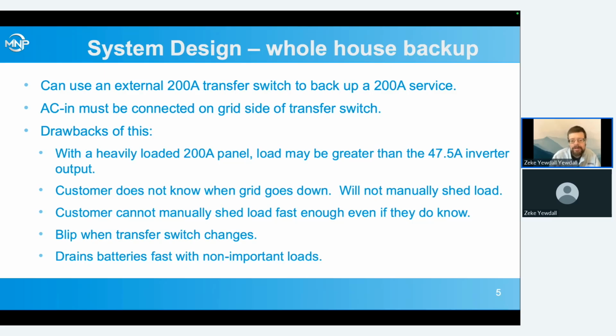And also, when you're using an external mechanical transfer switch, there's always a little blip, at least a second or two, when it switches over, because it's got to notice the grid went down and then switch. And they're usually designed to wait for a generator to come up to speed. Often those are waiting, say, 10 seconds. But even if you set them on the minimum, you're going to have a half a second to 1 second power blip when it changes, resets all the clocks, shuts the router off, things like that.